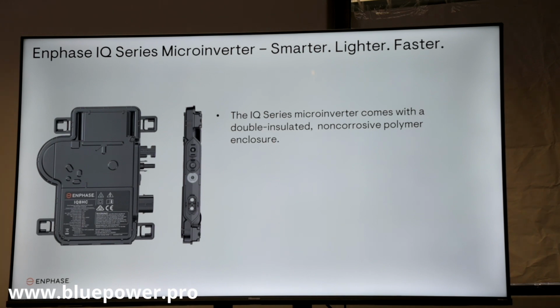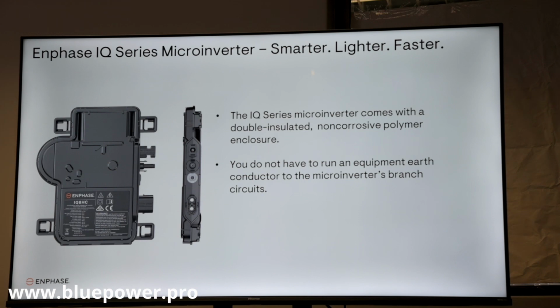When you install these microinverters, they clamp down on your rail underneath the panel. Now we all know that according to regulation, your installation must be earthed. Now these units are double insulated, non-corrosive polymer enclosure, so you'll see in that cable there's no earth conductor. So the microinverter itself doesn't get earthed, but your installation gets earthed, because as I said, it is double insulated.